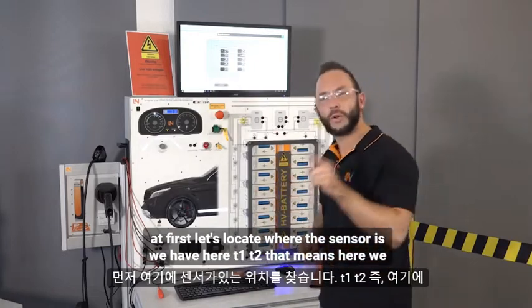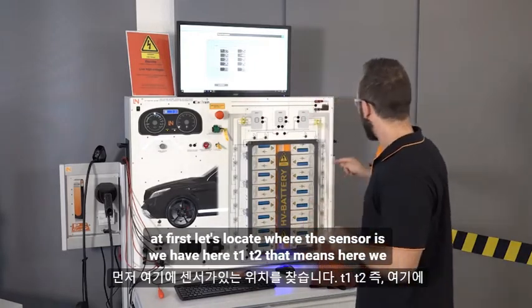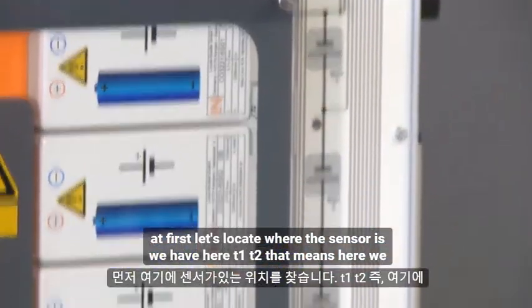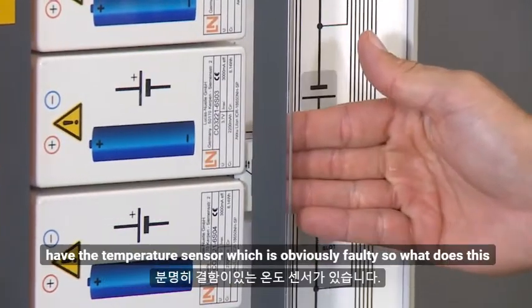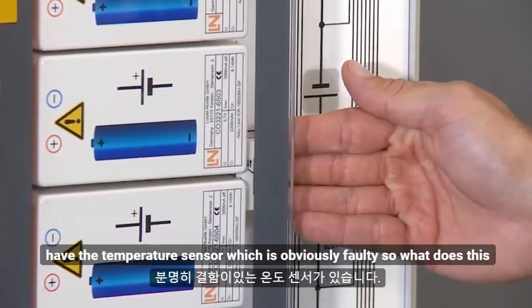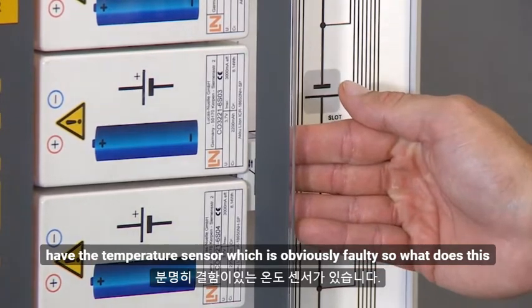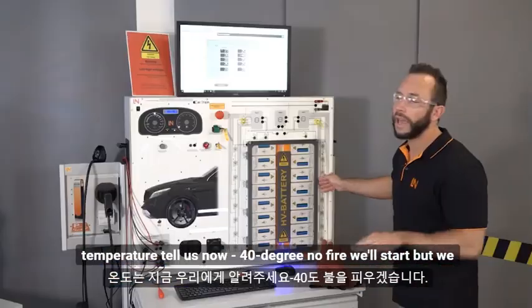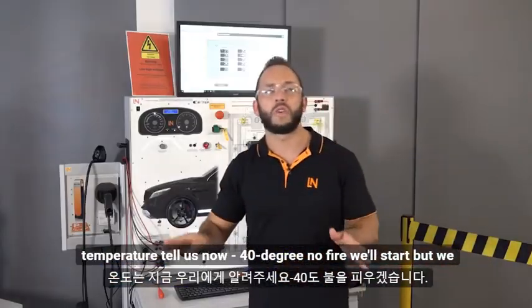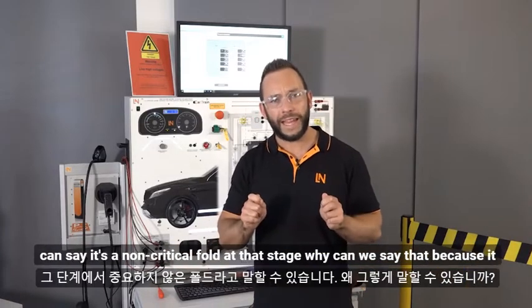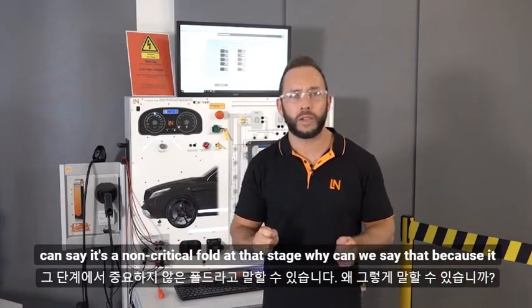We are all aware that this is not a normal temperature. So at first, let's locate where the sensor is. We have here T1, T2. That means here we have the temperature sensor, which is obviously faulty. So what does this temperature tell us now? At minus 40 degrees, no fire will start. But we can say it's a non-critical fault at that stage.